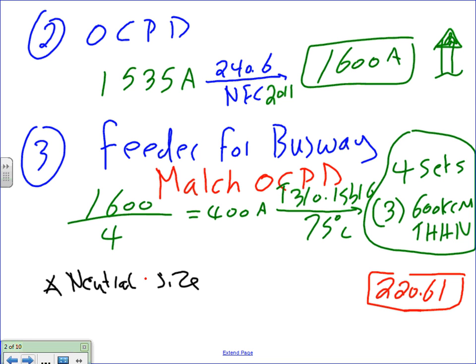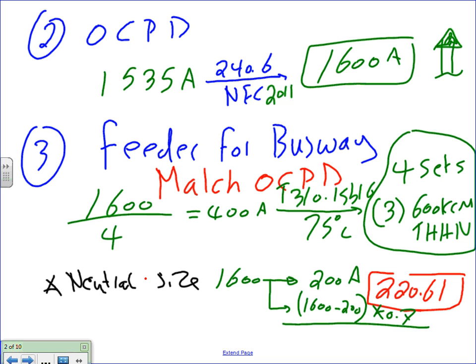I always default to 220.61 from the code, 220.61. If you guys go there, it will tell you the neutral size. The first thing you need to do is you take the 1600 amp that you size based on, okay? And you take the first 200 amp, these are sacred cows, don't mess with them. Anything higher than that, which is 1600 amp minus 200, cut these by 0.7. And where did I get this? From the code, and then add them.